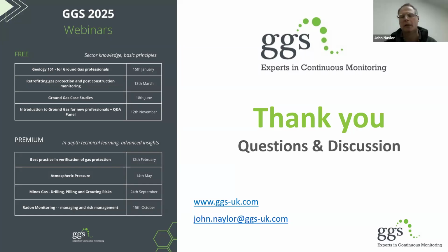Interesting question. So gas clam was the first generation of continuous monitors. We used gas clams. We've now got our own gas sentinels or air sentinels. You can configure a gas clam with different sensors that can give you better resolution that might be applicable to what you're doing. But generally, if you're going in with a normal setup, it's probably not good enough. You need to have better resolution sensors in there for methane and CO2. So what we're talking there, CO2 parts per million, preferably your methane, you need to be getting that down to maybe 50 ppm, ideally, for that kind of continuous monitoring.